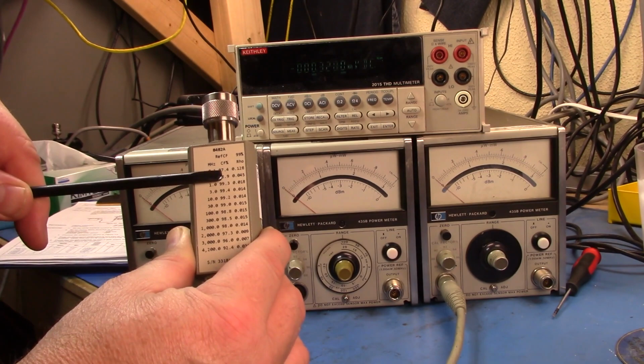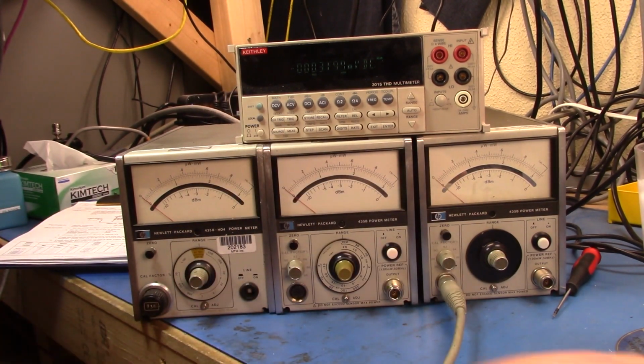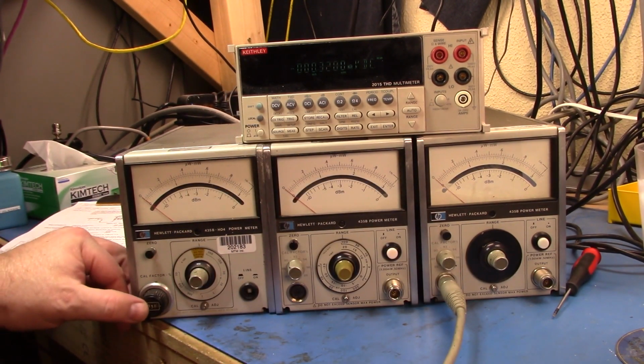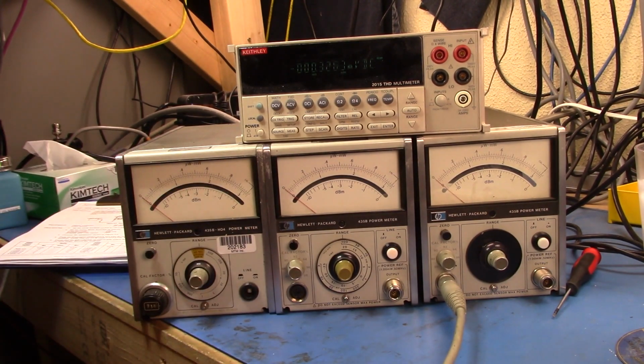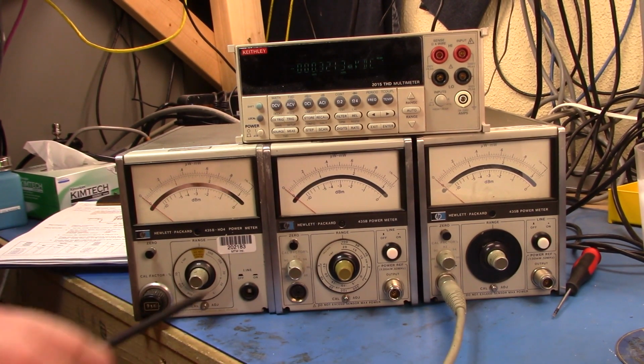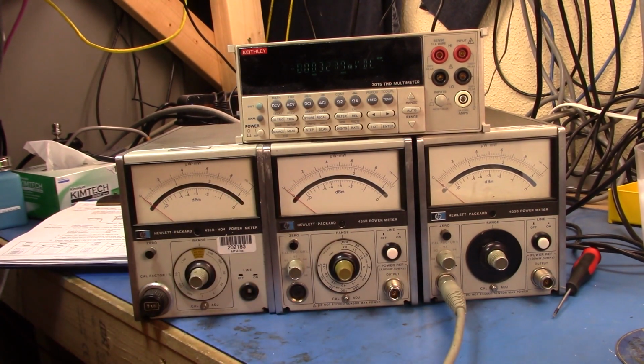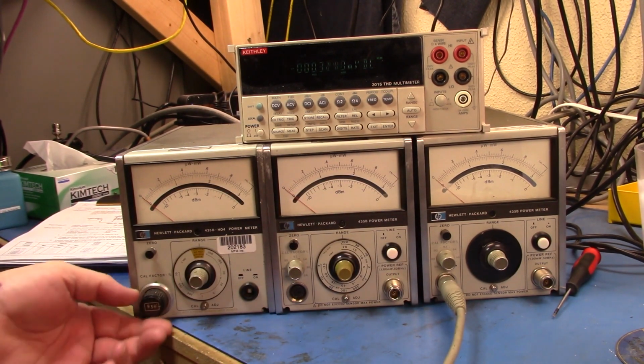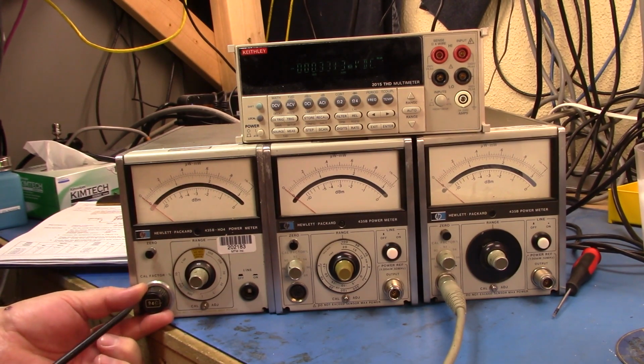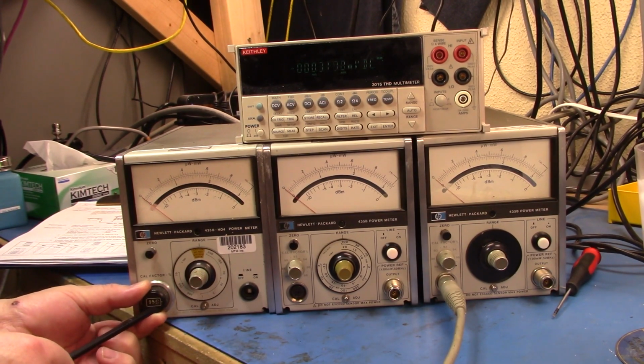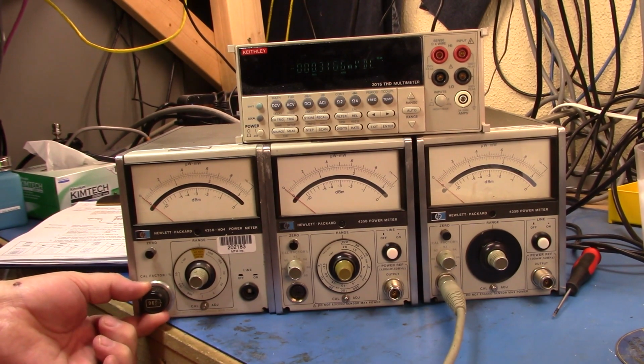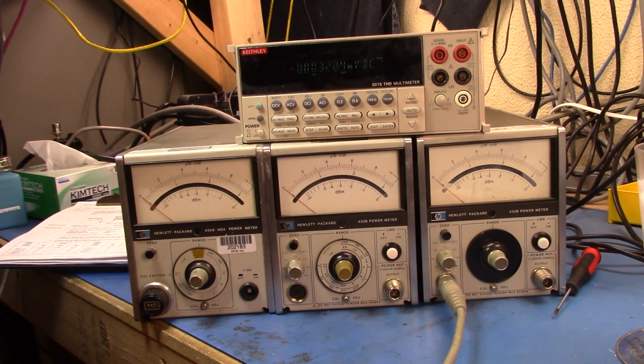But you'll see that the calibration factor is at least 0.1, possibly a little more. I'd have to look at the actual calibration document to see whether or not they provided more decimals. But in any case, the 435s only have a 1% calibration. So by using this, and you might be able to see it right here, we can move at greater than 0.1% accuracy around the calibration. So that must have been required at some point.